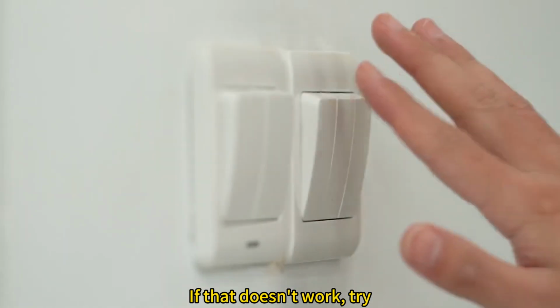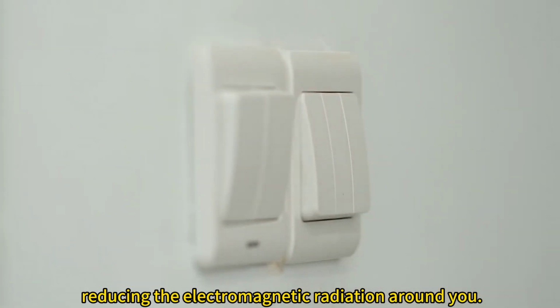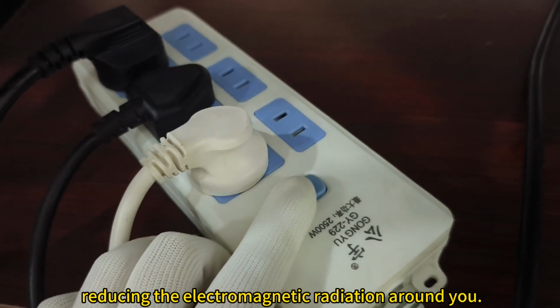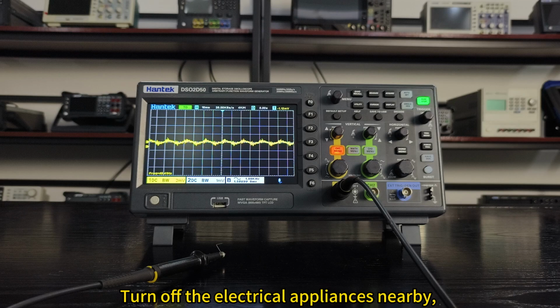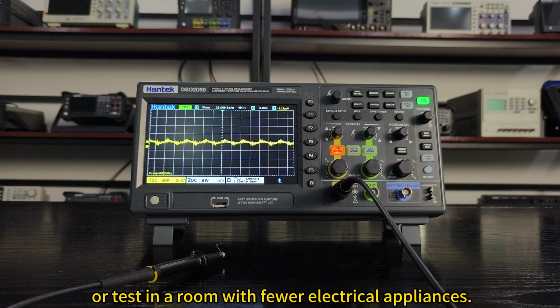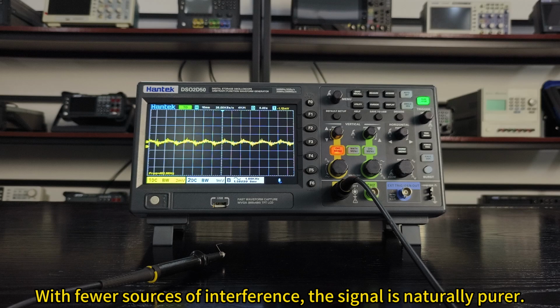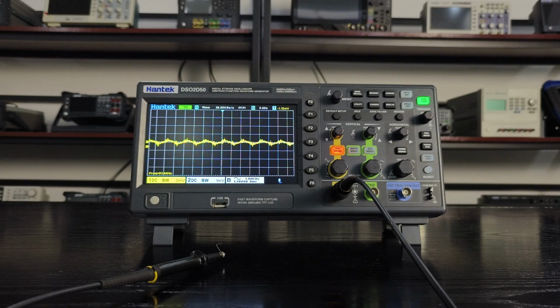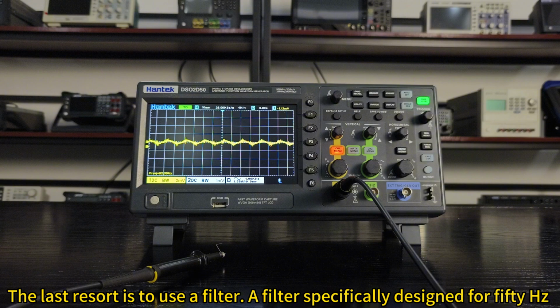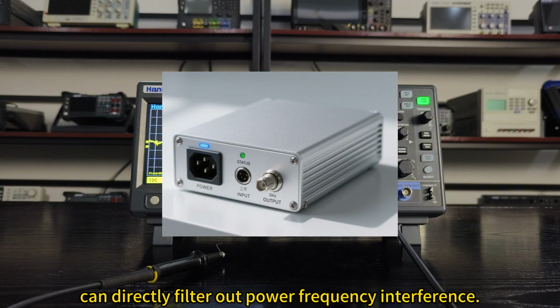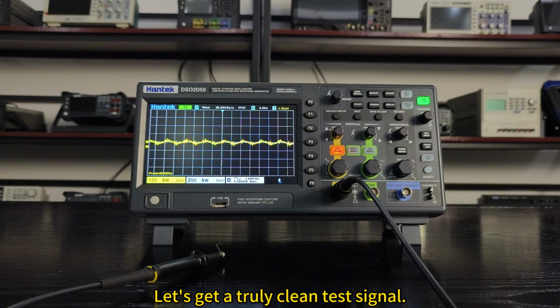If that doesn't work, try reducing the electromagnetic radiation around you. Turn off the electrical appliances nearby, or test in a room with fewer electrical appliances. With fewer sources of interference, the signal is naturally purer. The last resort is to use a filter. A filter specifically designed for 50 Hz can directly filter out power frequency interference. Let's get a truly clean test signal.